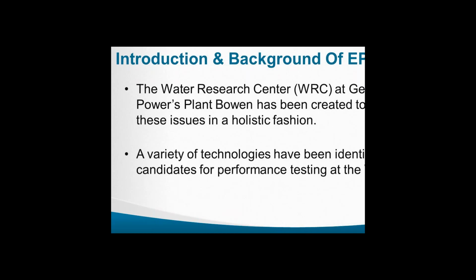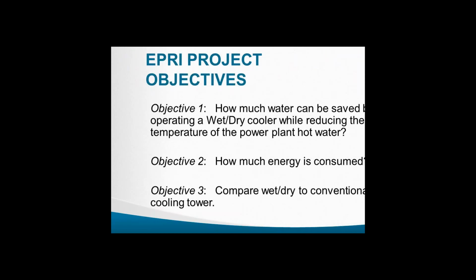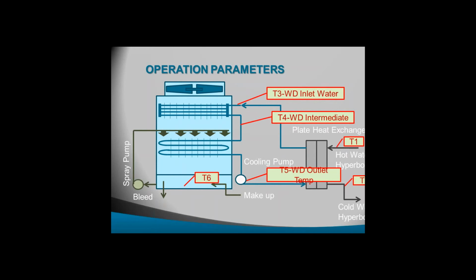So this is a Georgia Power location, and so they looked at a lot of technologies, and they wanted to see how much a hybrid tower would save for energy and water compared to a conventional cooling tower. So this is a dry cooler, dry coil on top, wetted coil on the bottom, using a plate and frame heat exchanger in line with the hyperbolic tower.